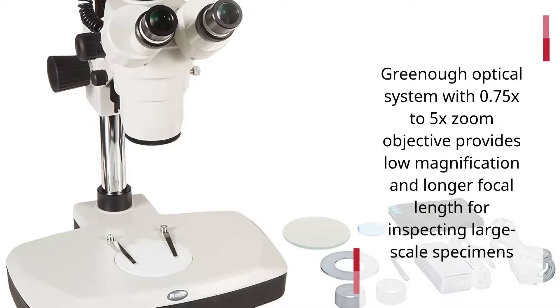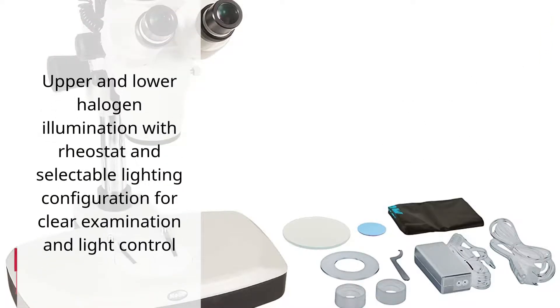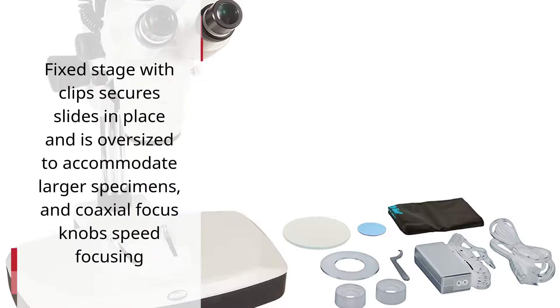The Greenough Optical System with 0.75x to 5x zoom objective provides low magnification and longer focal length for inspecting large-scale specimens. Upper and lower halogen illumination with rheostat and selectable lighting configuration allows for clear examination and light control. The fixed stage with clips secures slides in place, is oversized to accommodate larger specimens, and coaxial focus knobs speed focusing.